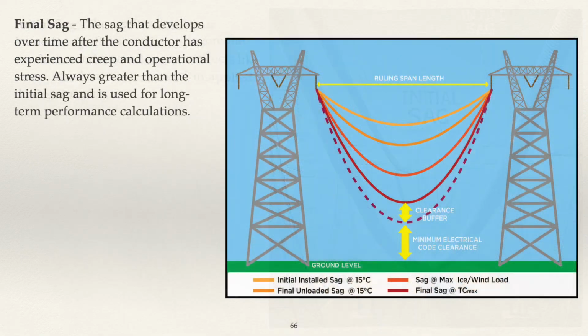Final sag. The sag that develops over time after the conductor has experienced creep and operational stress, always greater than the initial sag and is used for long-term performance calculations.